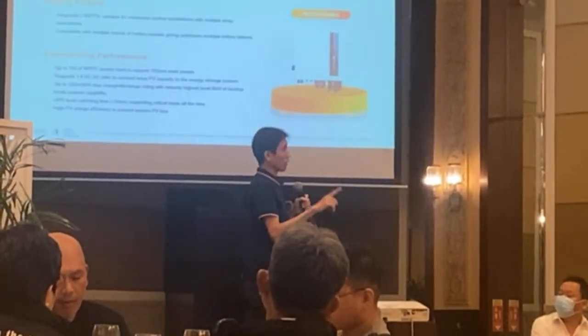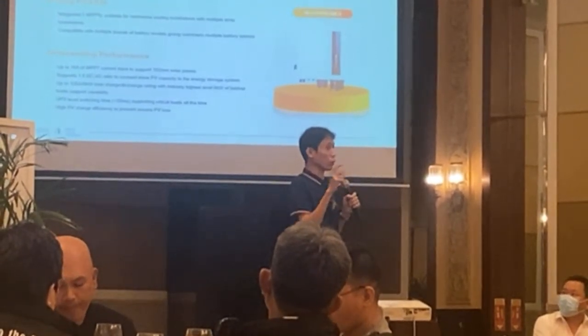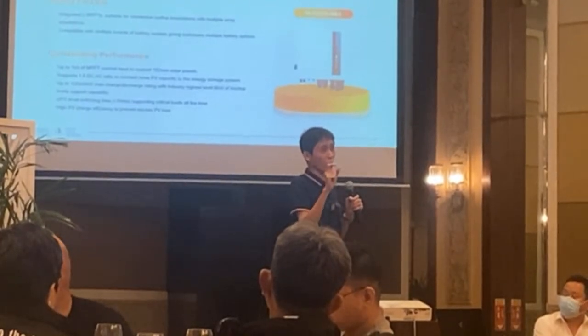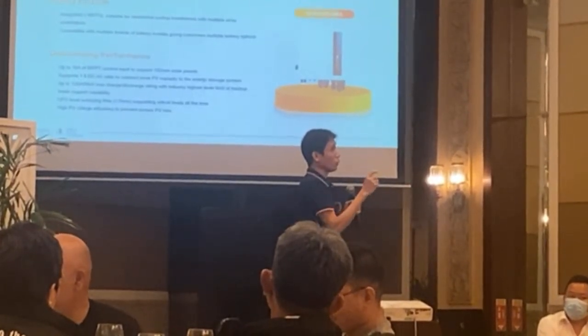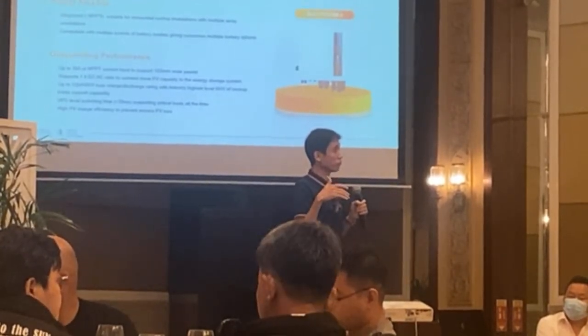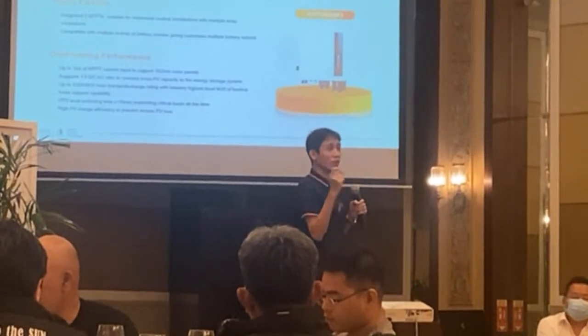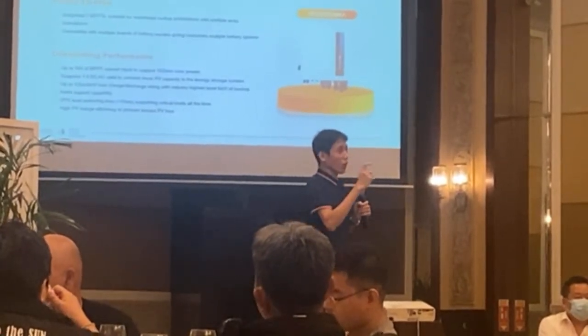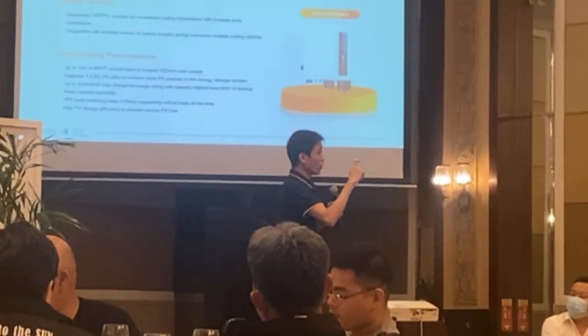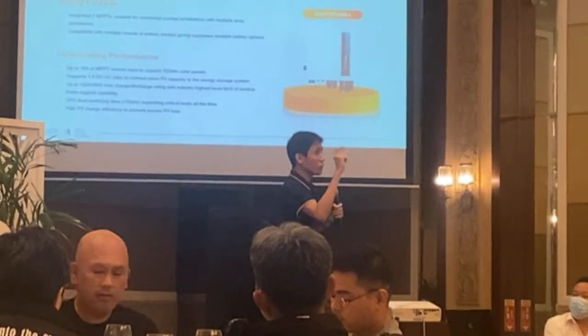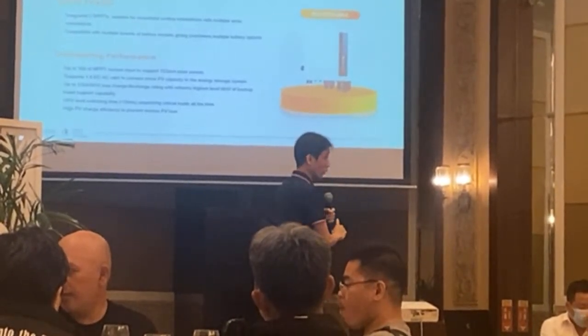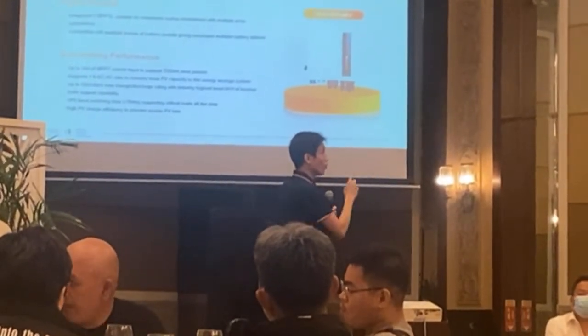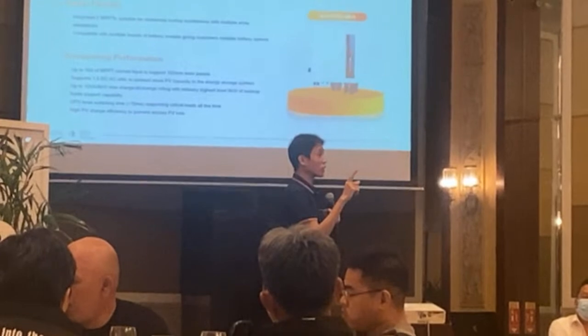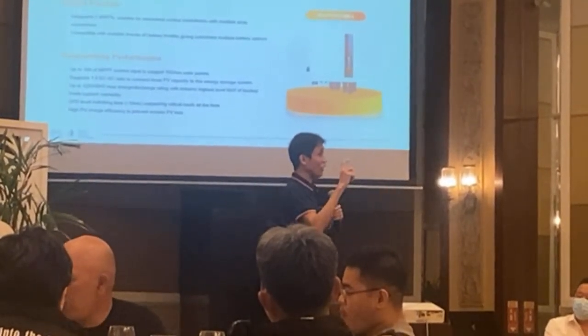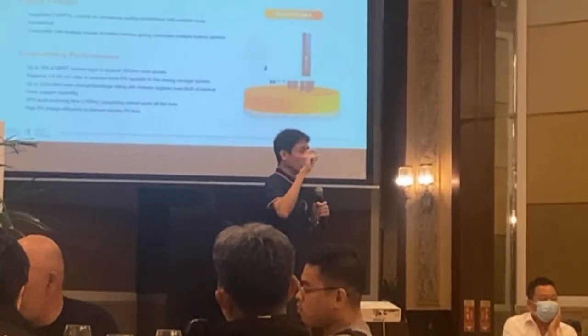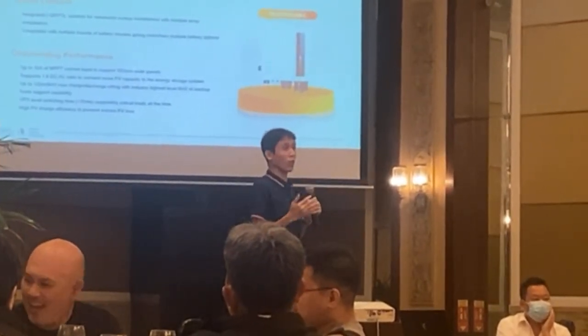Some ask already that, but I'm not suggesting it to use because they have a different ratio. Even though they have the same, I would say divided, they have the same 3,000 ratio, but the secondary coil is different. So because what happens is your meter is designed on that specific CT ratio, not on the inverter that will adjust. So what will happen is your inverter will just read whatever is being fed by your meter. So there's a danger in it. Now, if you think during the replacement is okay, you have to observe.